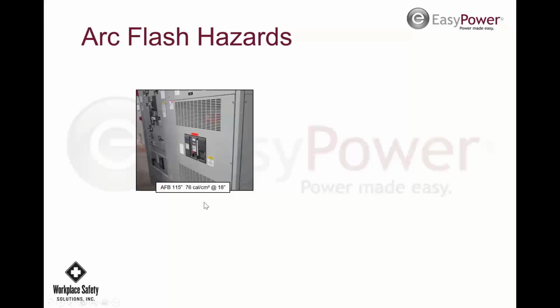So we go in to do the study, and they're thinking they're doing well, but the arc flash boundary is 115 inches, and it's 76 calories per square centimeter. And they're like, why is it so high? Well, the reason it's so high is that it's still got the same transformer outside that fed the 4,000 amp switchgear. It's a 5 MVA transformer, a large transformer, and it has low impedance because it's a 1962 vintage transformer, probably older than that. That caused an immense amount of fault current to be available and brought the arc flash level up very high.